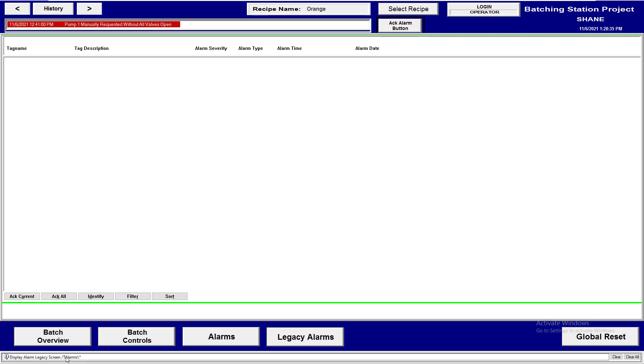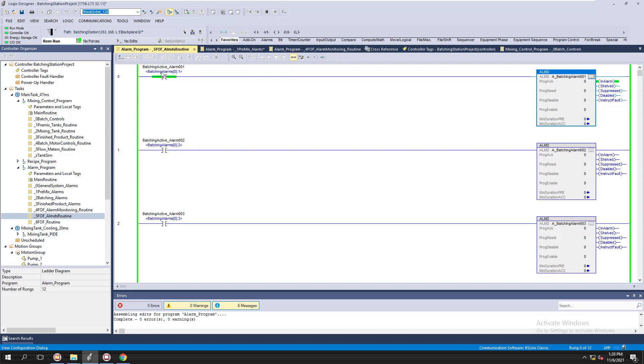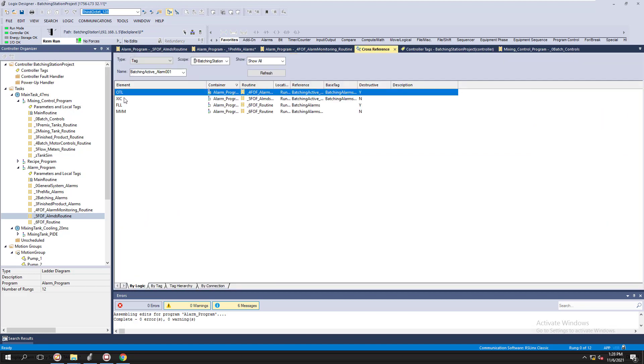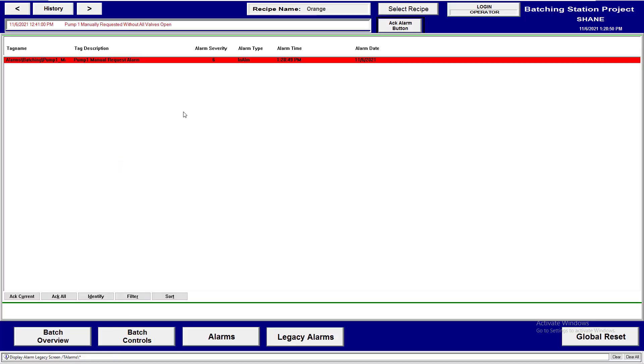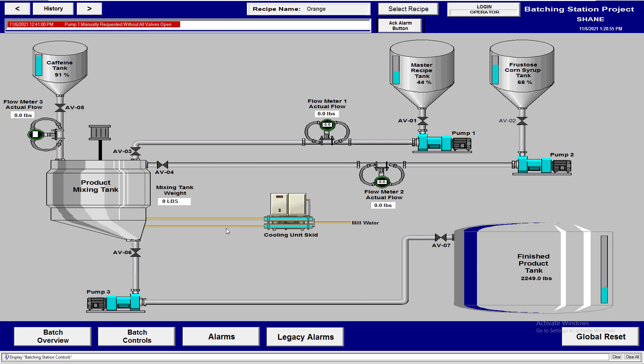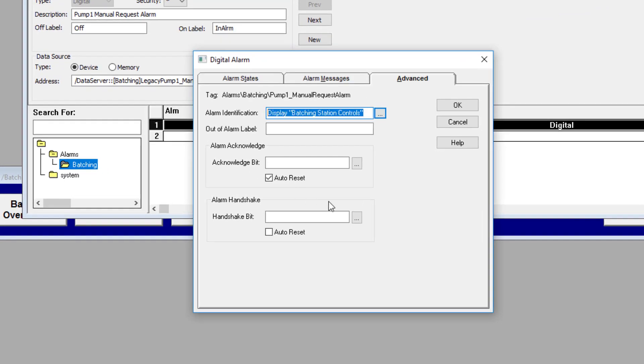Let's make the alarm active by going over here and triggering this on, just like this. Now if I come over here and click the identifier, it will take me to the screen that this alarm is associated with. That's how that identifier works — it's a very powerful tool for HMI operators so they can navigate directly to where that alarm is located.